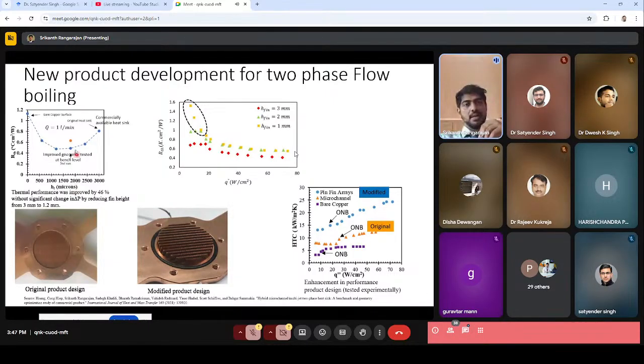This is the commercially available cold plate's thermal resistance, which we tested. As we kept reducing the height of the fins in the cold plate, the thermal resistance dropped, reconfirming that there's a huge opportunity to optimize the geometry of this cold plate, because the available geometry is not the optimal geometry.